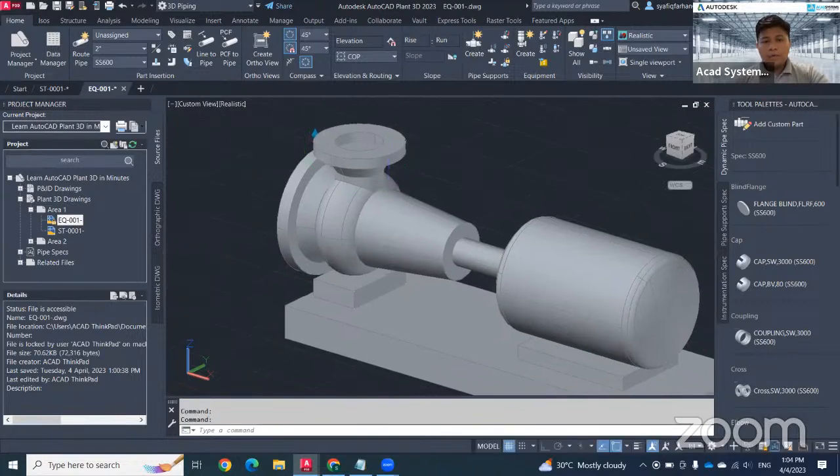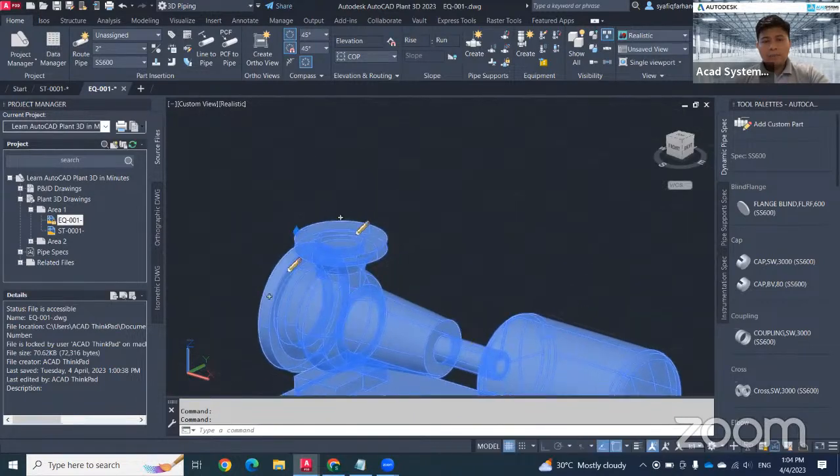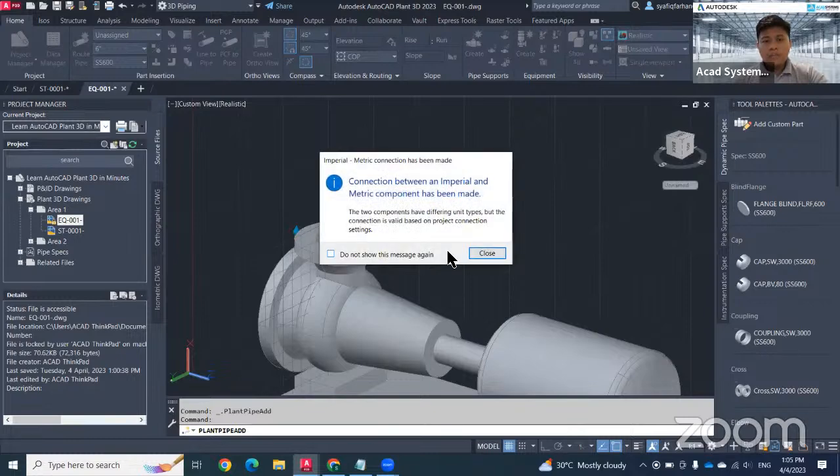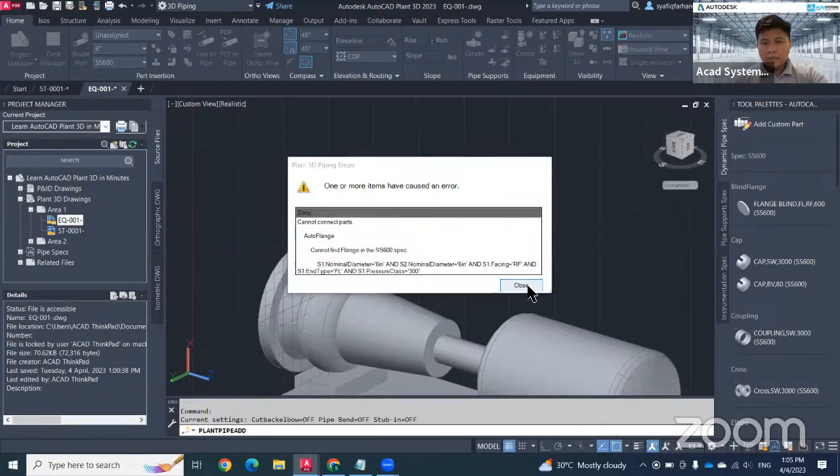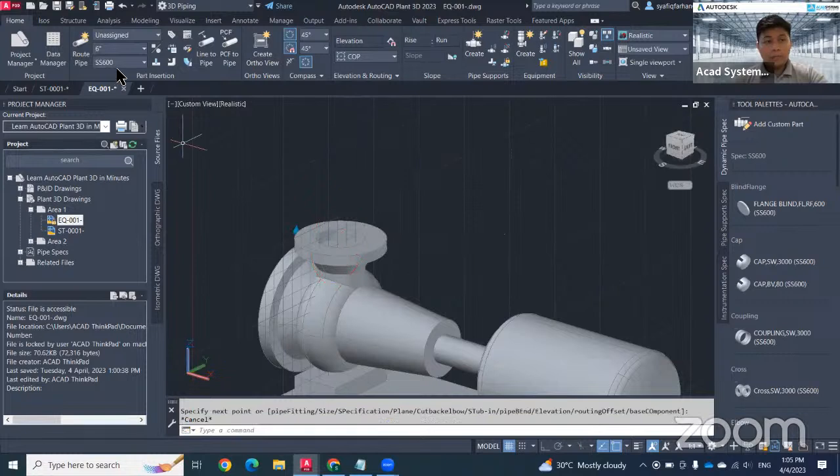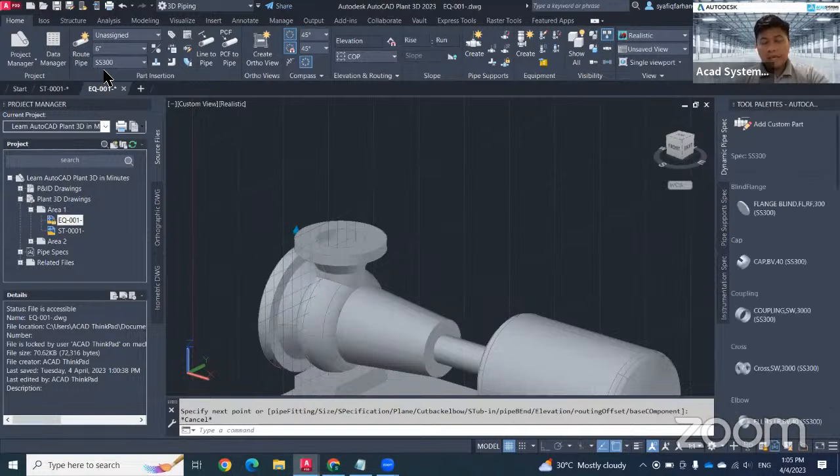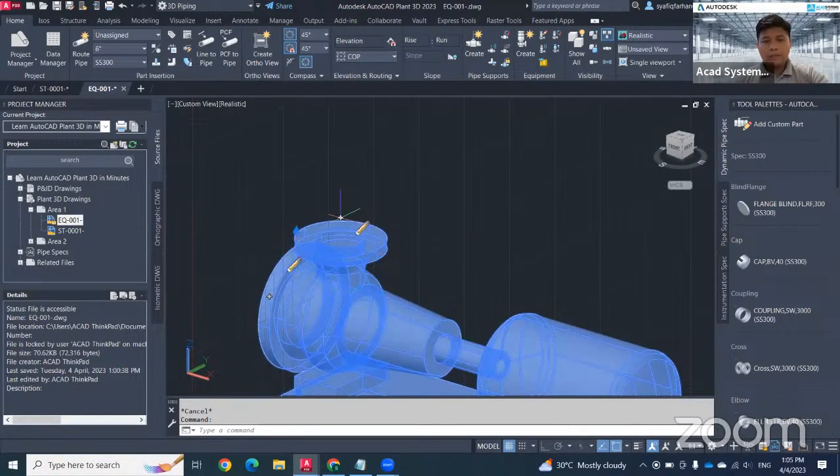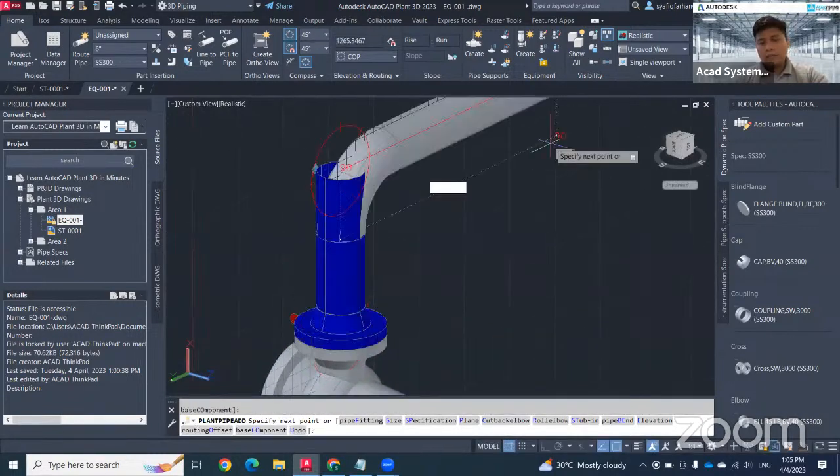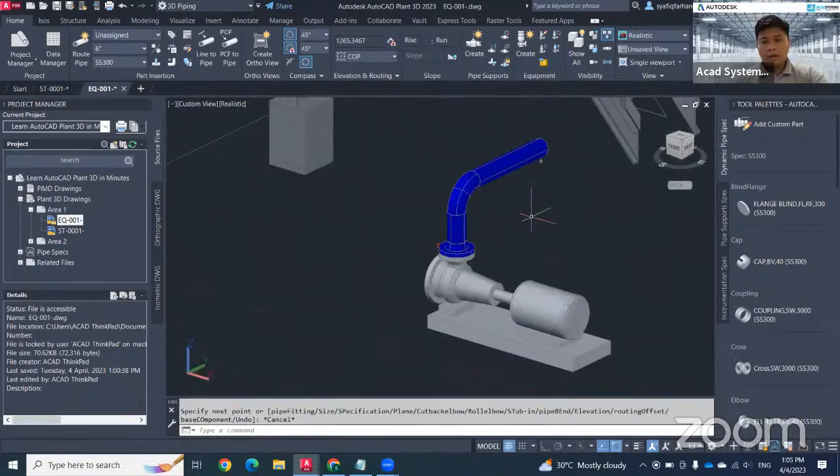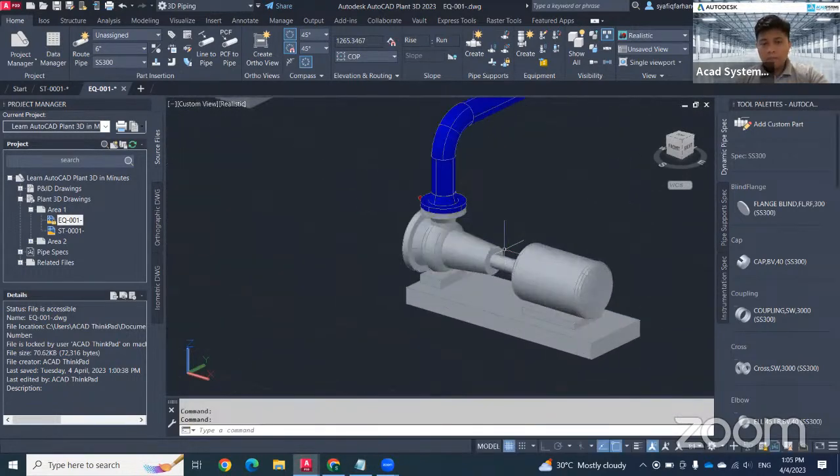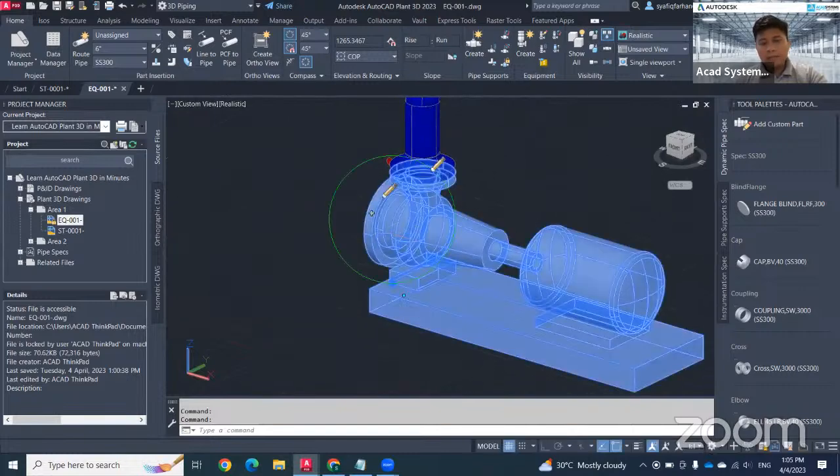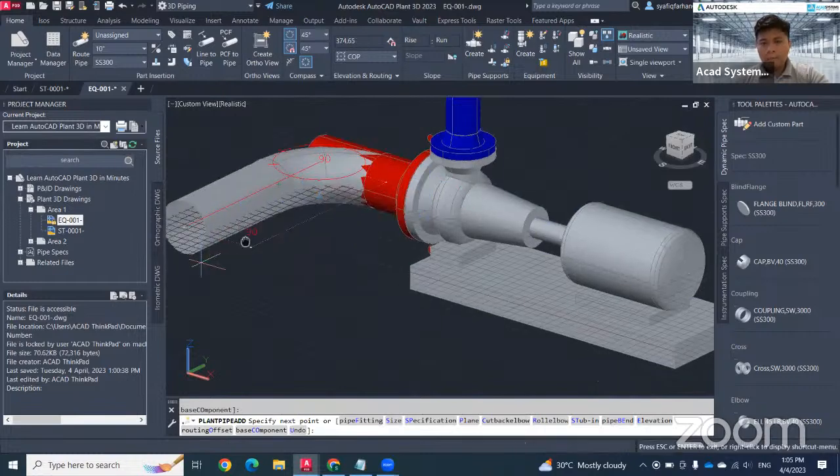To create a pipe, you will face this kind of problem if you are not using the correct spec. Make sure that since your nozzle is set to have a 300 pressure class, make sure that you are using also the 300 pressure class, which is this one, SS300. When you use the proper spec, it will directly generate auto flange. If you are using a different spec, different pressure class or nominal diameter, then you will face that kind of problem.